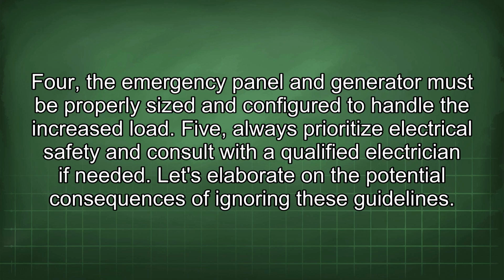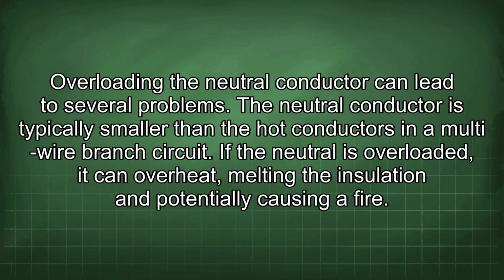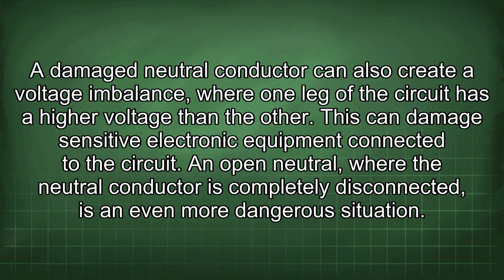Let's elaborate on the potential consequences of ignoring these guidelines. Overloading the neutral conductor can lead to several problems. The neutral conductor is typically smaller than the hot conductors in a multi-wire branch circuit. If the neutral is overloaded, it can overheat, melting the insulation and potentially causing a fire. A damaged neutral conductor can also create a voltage imbalance where one leg of the circuit has a higher voltage than the other. This can damage sensitive electronic equipment connected to the circuit.